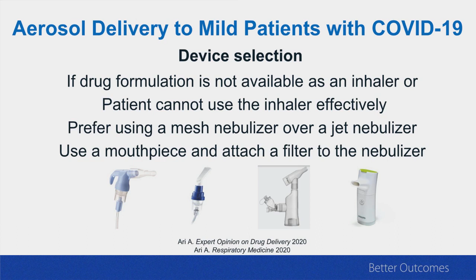Every time you use a nebulizer, use it with a mouthpiece and attach a filter to the exhalation port of the nebulizer. Now you're wondering why you need to put a filter to the exhalation port. Let me explain it to you. Attaching a filter to the nebulizer is 93% effective in capturing exhaled aerosol droplets. It's a very basic procedure, but it is very effective. So if you're using a jet nebulizer, all you need to do is to attach a bacteria filter to the 6-inch large bore tubing like you see in the slide. If you use a mesh nebulizer, you can attach the filter to the mouthpiece.